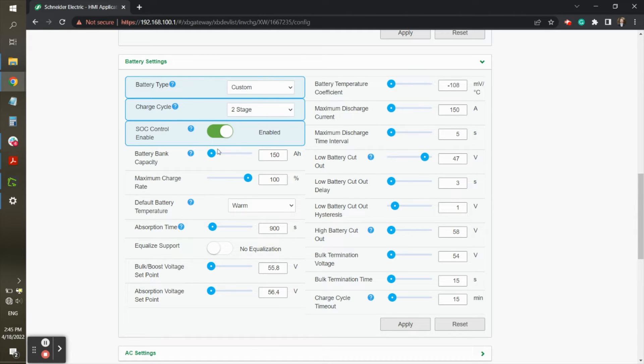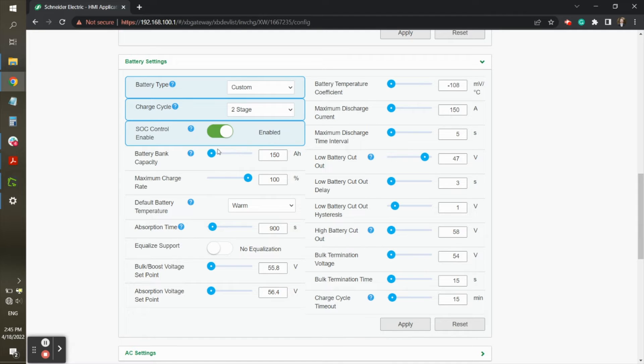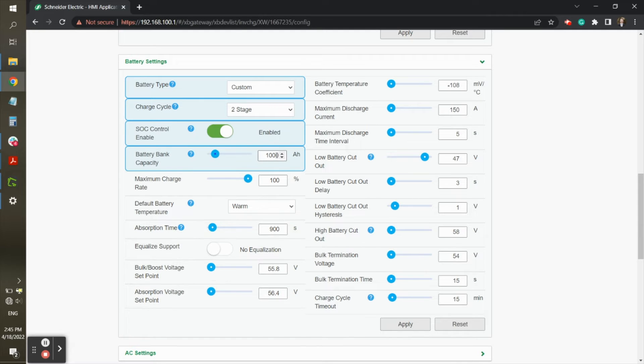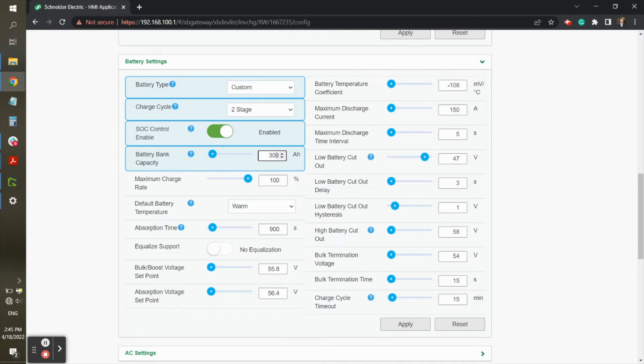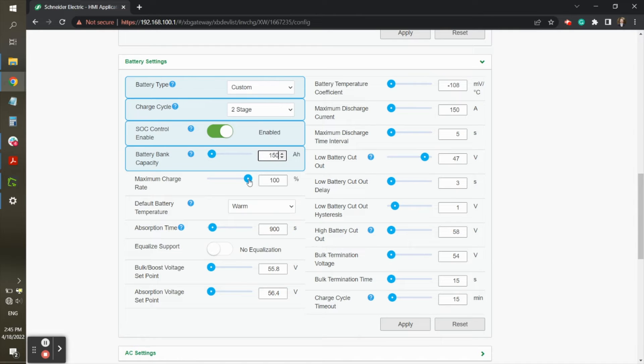SOC, or State of Charge Control, can be enabled if using a Schneider battery monitor, or disabled if you want to use battery voltage as a means of triggering Grid Connect, Auto Gen Start, and so on. The battery bank amp hour capacity should be calculated by multiplying the number of HAB batteries in the bank by 150 amp hours. In this case, we have just one HAB, so we'll leave it at 150.